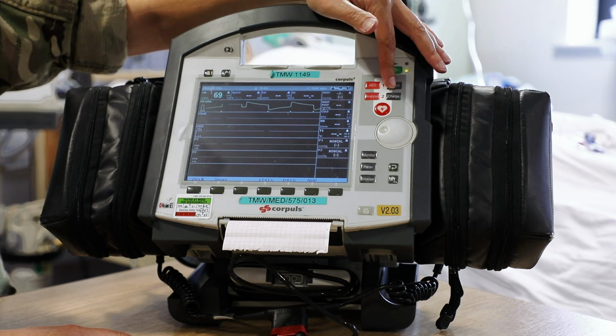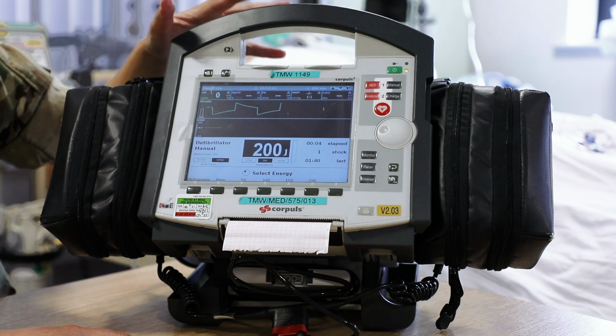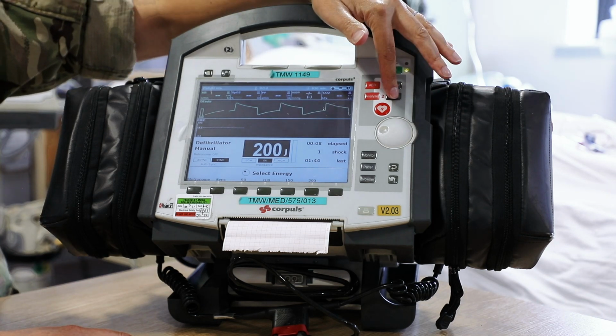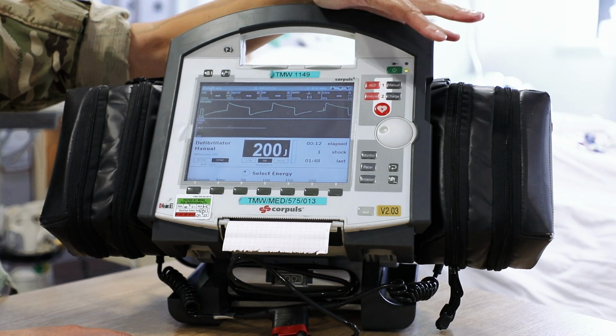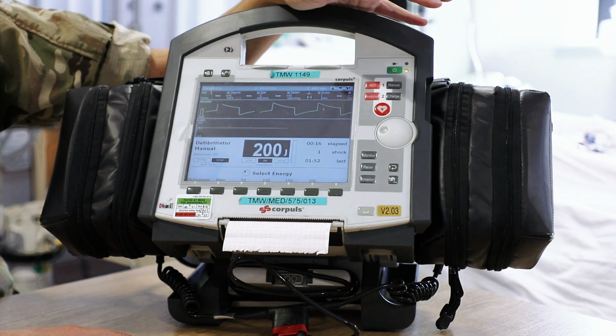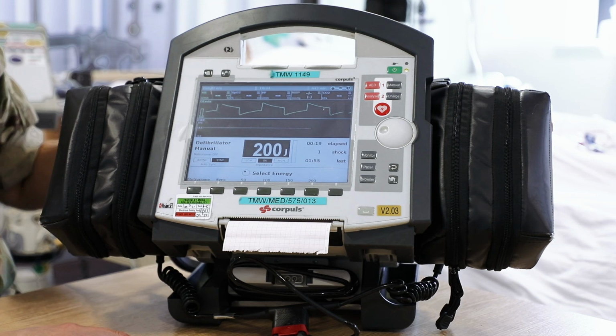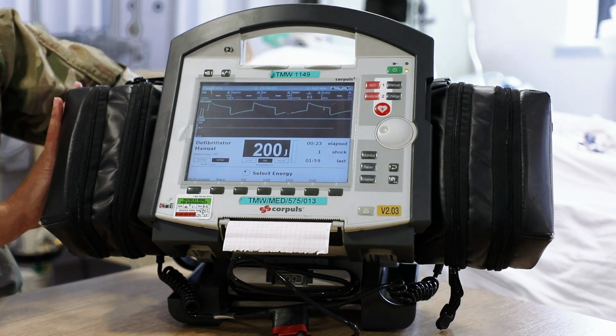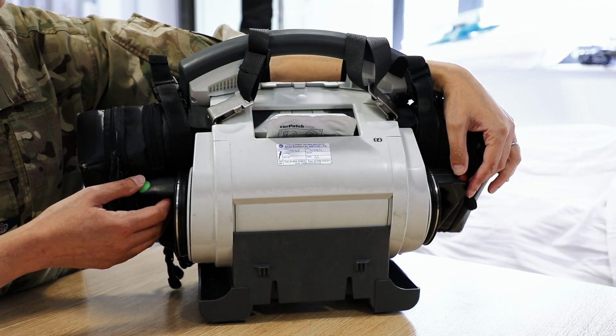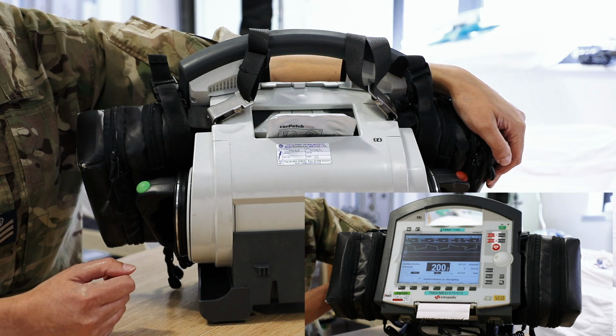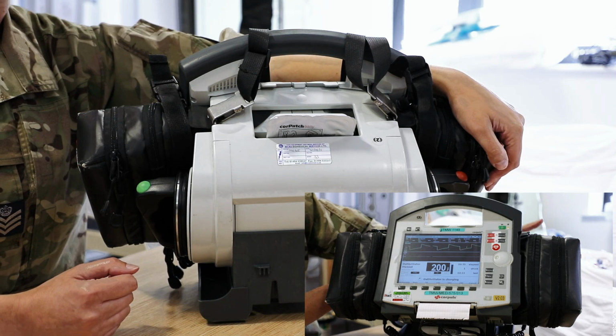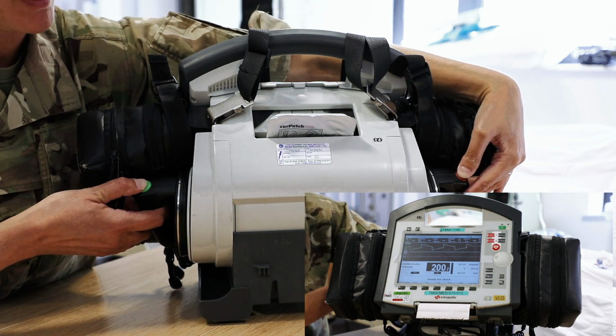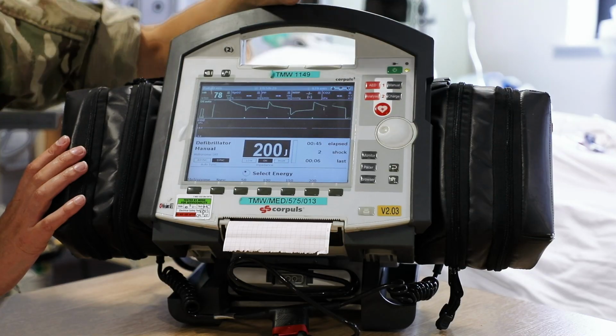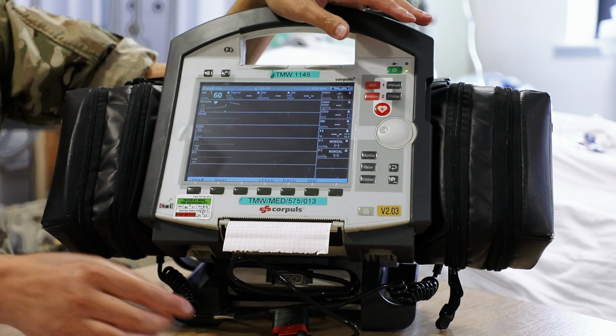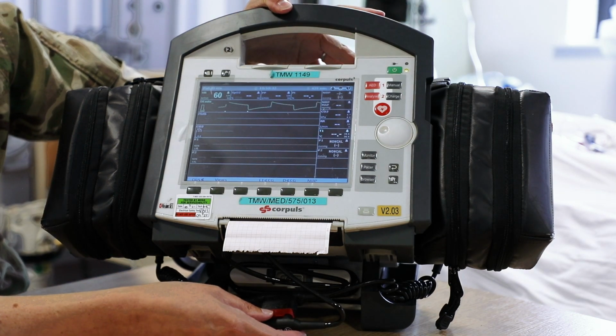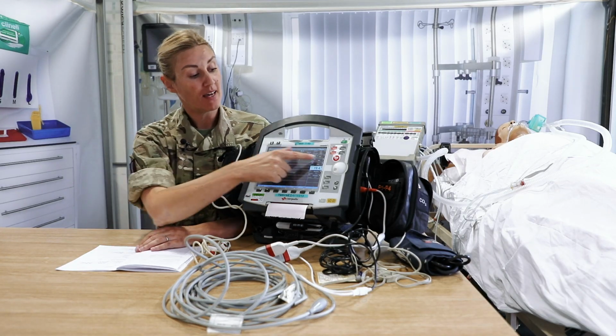Now when we press the manual button, it's now coming on as a defibrillator using the external paddles. So you'll notice that you can no longer use the charge button on the screen, because we're going to use the buttons attached to the paddles themselves. Leaving the paddles in their housing, so this is again the safety discharging box, they're going to discharge into the machine itself. We're going to just press one button on the top of a paddle to charge, and it doesn't matter which button you push, just one of them, and then we're going to press and hold both to deliver the shock. And once you're happy that that second shock has been delivered, disarm your defib and return your red master cable to its original housing.